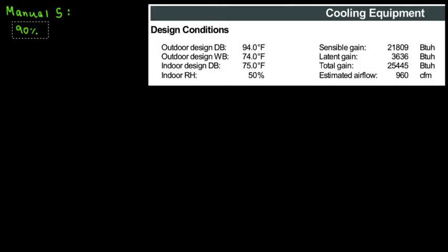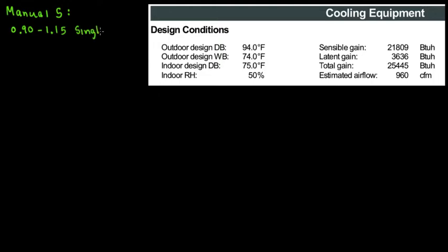We're going to do this as the Manual S states. They are indicating capacity factors, or oversizing factors, however you want to name it. The capacity factors are 0.90 to 1.15. You can either write this in percentage or in decimal. That's going to be for single speed compressor.